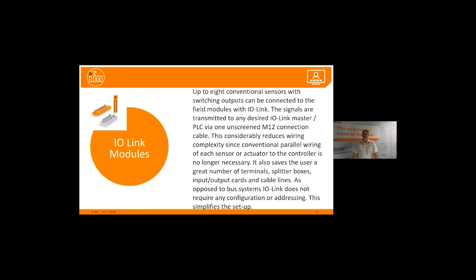It also saves the user a great number of terminals, splitter boxes, input and output cards, cable lines, and points of failure once again. As opposed to bus systems, IO-Link does not require any configuration and addressing. That's with the ASI field modules, you have to give it an address. And this simplifies the setup.